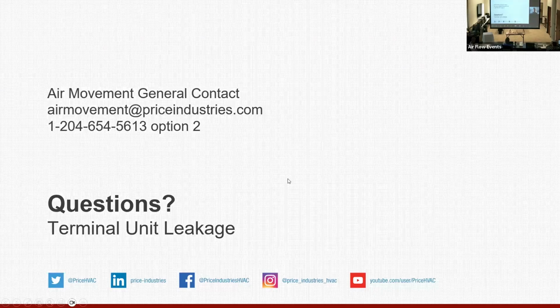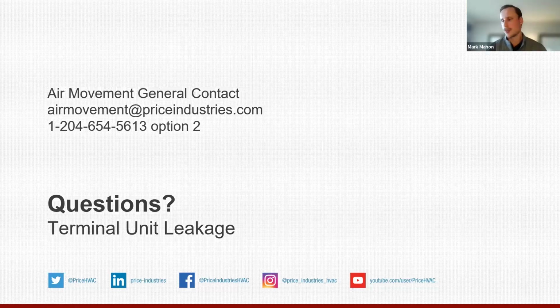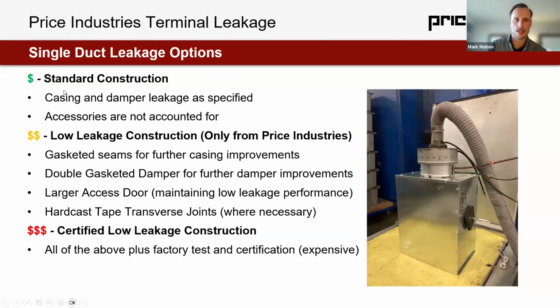Who's requiring the certified? Is that like is LEED requiring? Owner. The owner wants. Or just the owner? Okay. It's coming from the owner primarily. So we see that in Texas. We see that sometimes in California. I think most manufacturers historically haven't had an option in between. So if a really harsh leakage spec comes up, harsh, I would say required leakage spec comes up, we see manufacturers defaulting all the way to the high cost option. That's why we've inserted this kind of medium option that's the same construction, just no certification. And that's why I recommend it as well.